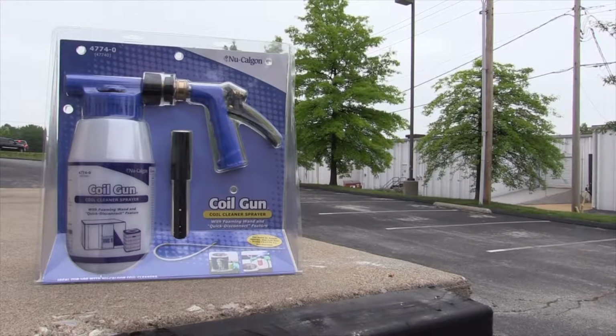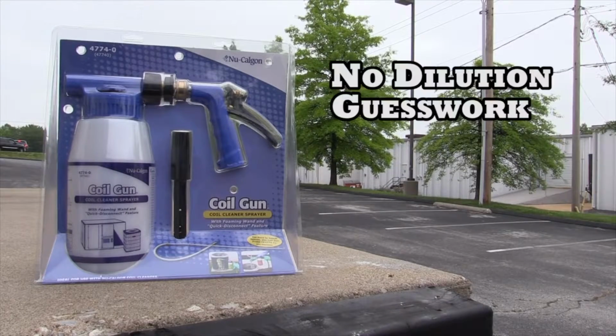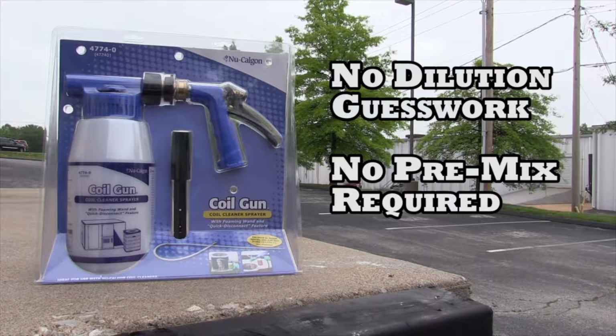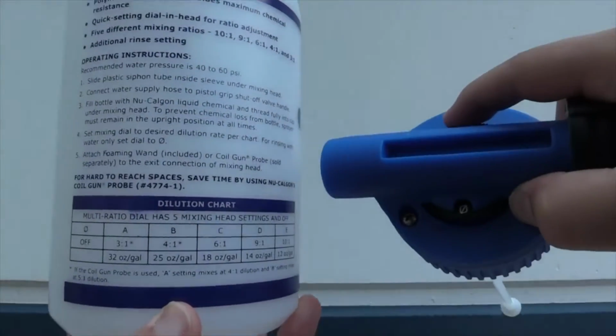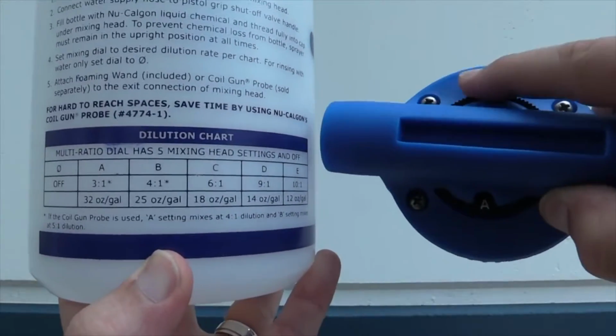Use of the Nu-Calgon coil gun takes the guesswork out of the dilution process. Unlike other sprayers, which require you to combine water with the coil cleaner in a separate step, the coil gun does the mixing for you thanks to the specially equipped mixing head that siphons the cleaner through the coil gun when the sprayer handle is depressed.